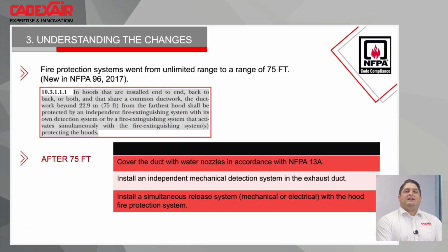I will say everybody that wants to list a fire protection system will go for 75 feet of ductwork. And they're doing the test, and they really have at the UL facility a ductwork doing a big S on the side of the wall for over 75 feet. So when they put grease, they do a fire test. And if you comply with the test, UL says, congratulations, you passed the test. And UL was saying, if you complete the 75 feet test, you have unlimited range for your fire protection system.